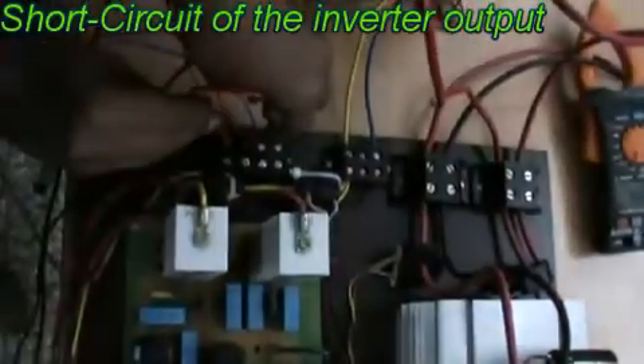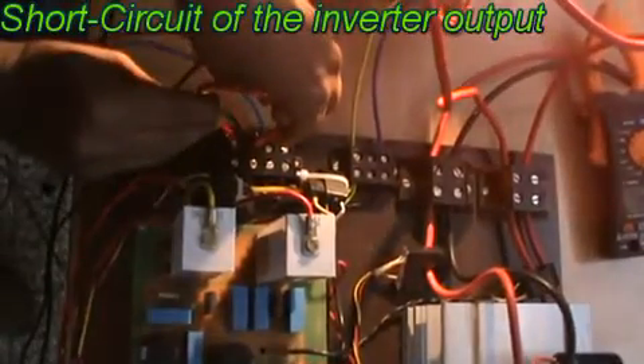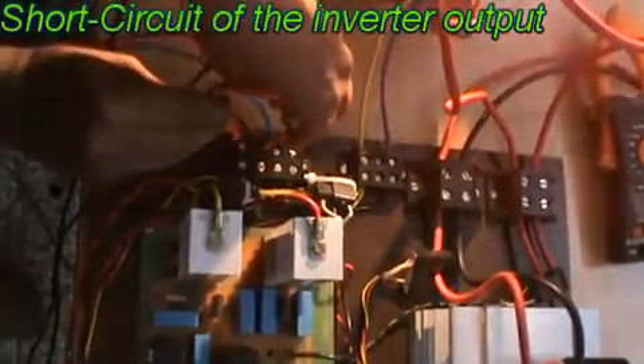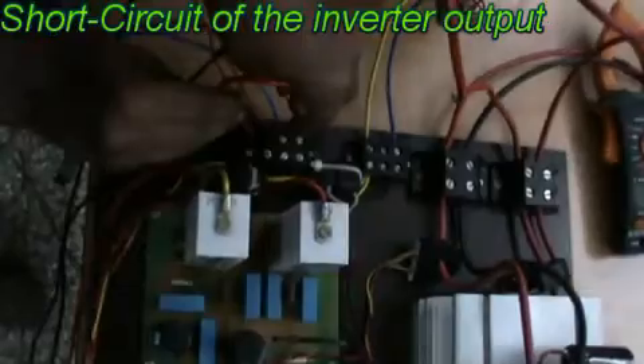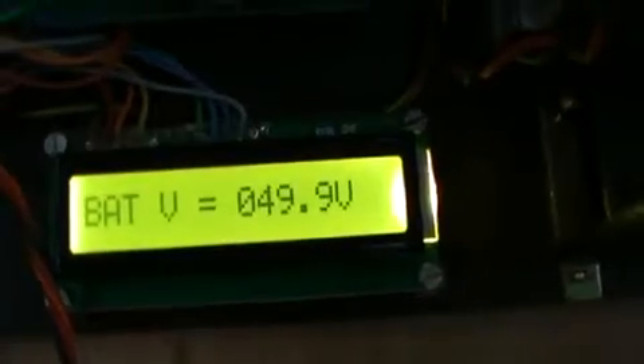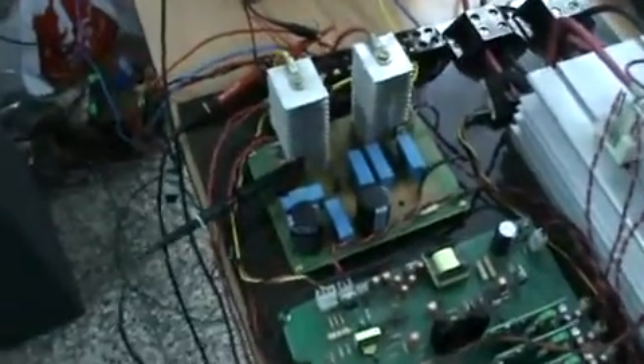During short circuit also, the cycle by cycle current limiting action will protect the IGBTs. The system will not immediately trip during short circuit. It will trip only if the short circuit remains for more than 3 seconds. This will help in the starting of surge loads. The inverter to mains and mains to inverter changeover is always synchronous with mains.